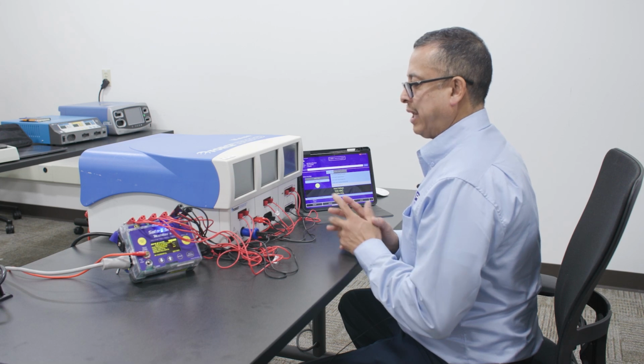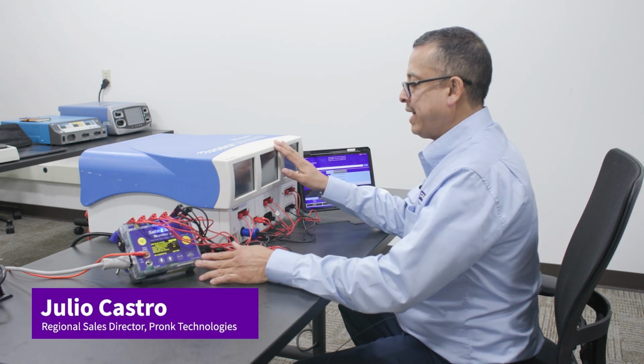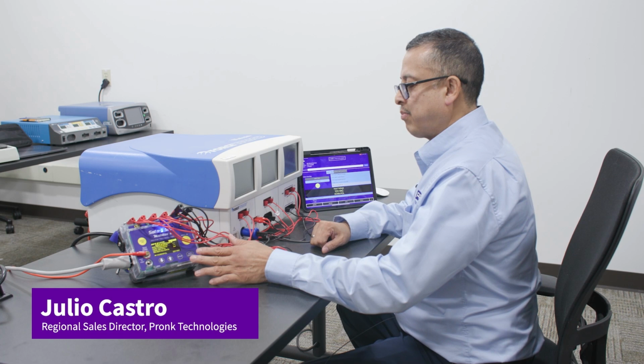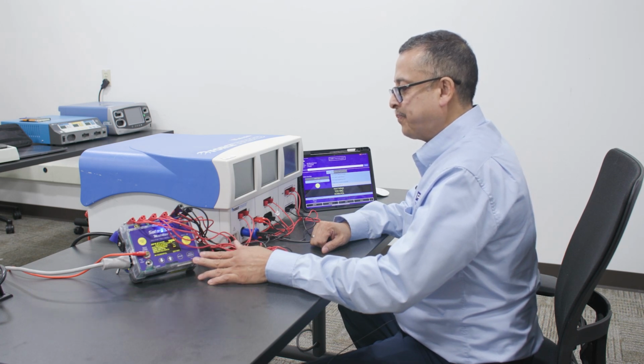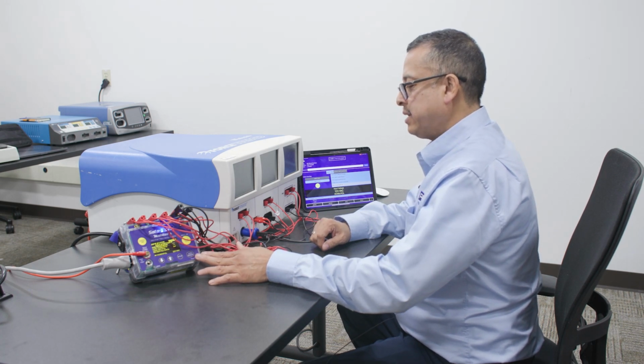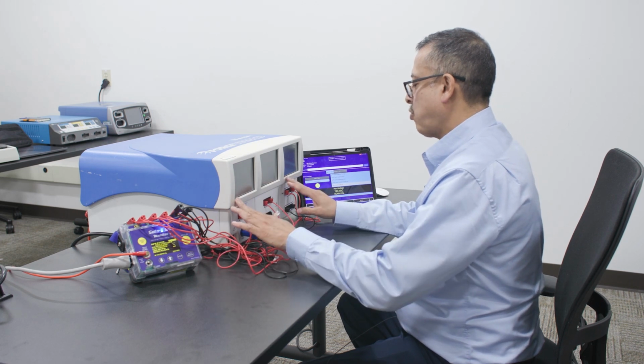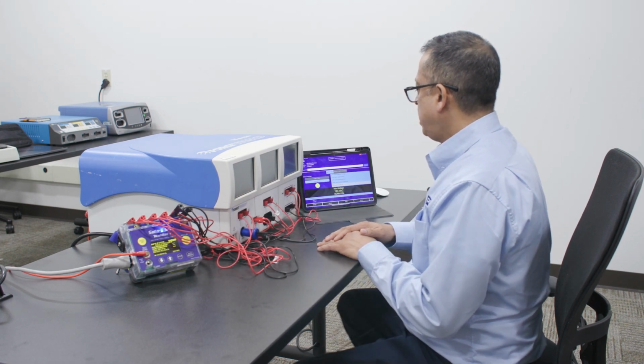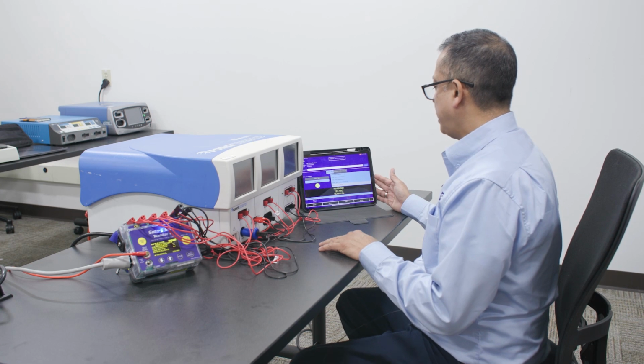We're going to go ahead and do electrical safety testing on this ForceTriad ESU utilizing the Pronk Safety Sim Safety Analyzer. We need to get the unit ready to do the testing per the manufacturer's requirements that are in the service manual, and we're going to do that via the Pronk Mobilize app.